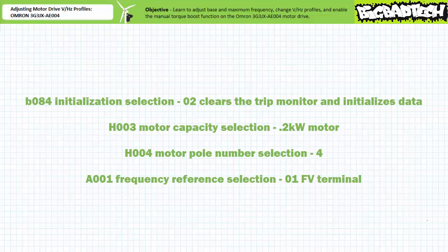We'll initialize the drive to a default state and clear any errors using the initialization and protection parameter B084. Then we'll program it to recognize a 200 watt motor with a nominal rotational speed of 1800 rpm using the motor settings parameters H003 and H004. Finally, we'll program the drive to recognize an external speed potentiometer input using extended function parameter A001.